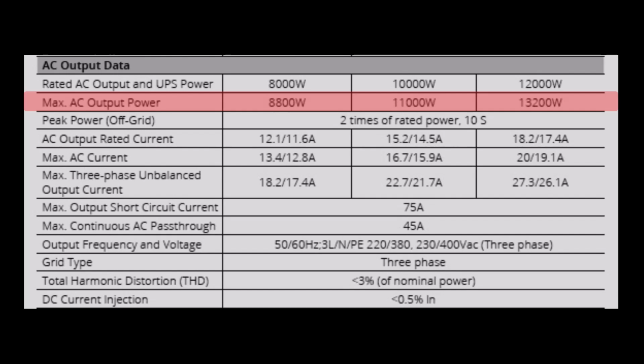The peak power off-grid is 2 times of the rated power for 10 seconds. In other words, the unit could receive 24,000 watts for 10 seconds. Obviously, you'd combine this with some sort of cutout fuse because you don't want to ruin your expensive inverter.